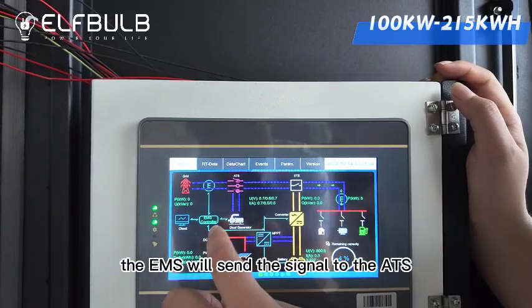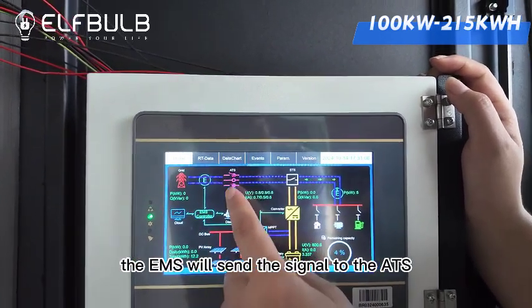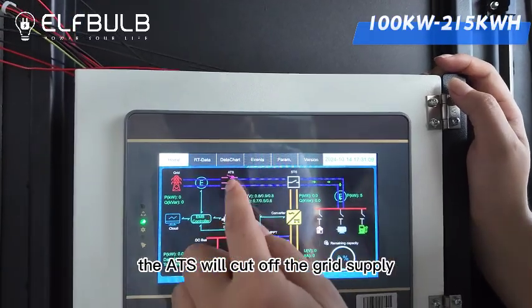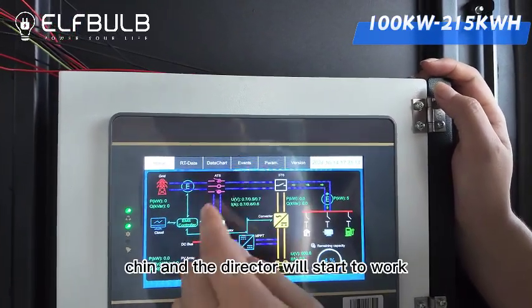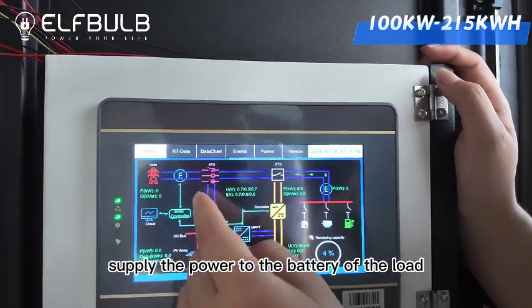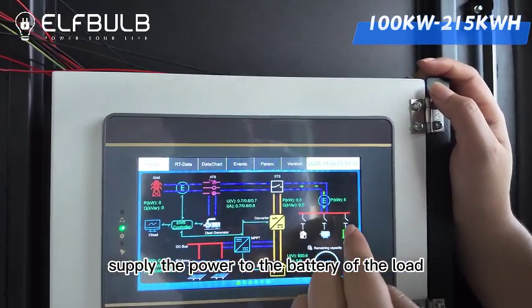For example, if there's no power from the grid, the EMS will send a signal to the ATS. The ATS will cut off the grid supply chain, and the generator will start to work, supplying power to the battery or to the load.